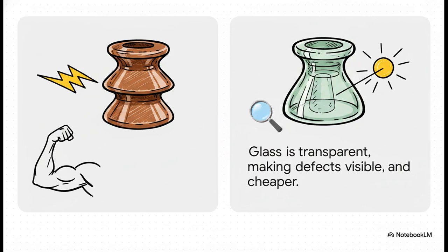For a very long time, porcelain was the absolute king of the grid. When it's highly pure and homogeneous, meaning no internal air bubbles, porcelain brings incredible compressive strength, plus amazing electrical resistance, capable of blocking 60 kilovolts per centimeter of material.